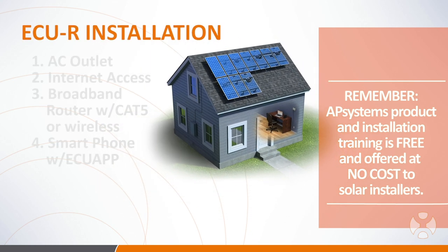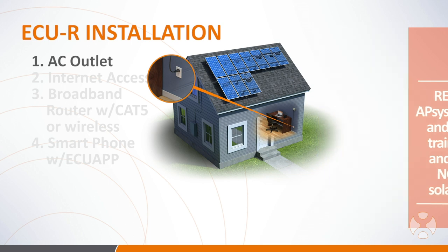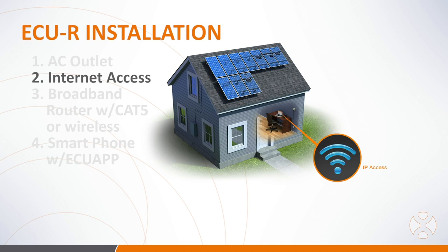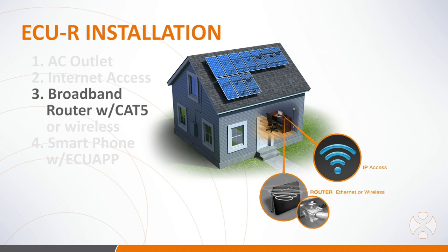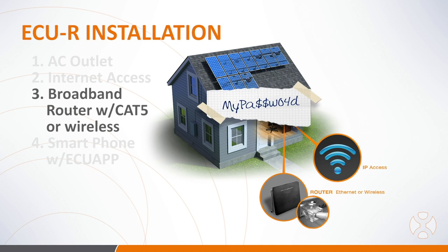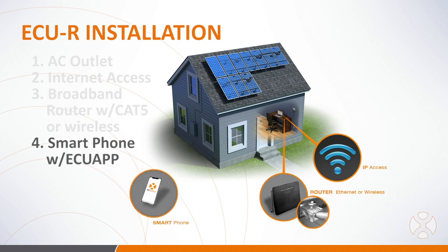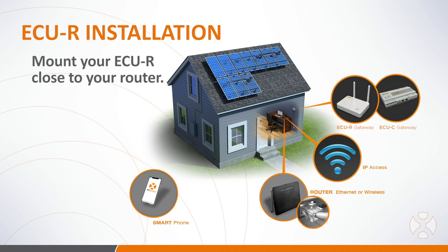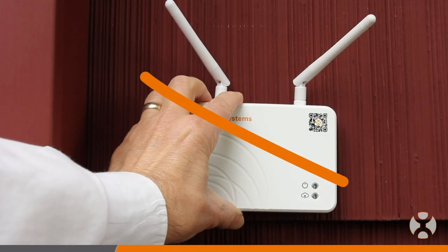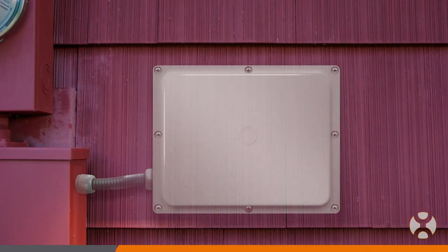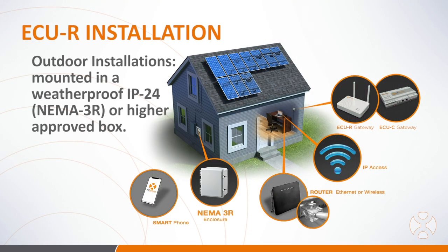In preparing to install the ECUR, be sure to have the following necessary components available: a dedicated standard AC electrical outlet located as close to the array as possible, a broadband internet connection, a broadband router with a CAT5 ethernet connection or a wireless router — if wireless, obtain the router password from the home or site owner — and a smartphone with the AP Systems ECU app installed. Note that a smartphone with Wi-Fi capability is required. When selecting an installation location, choose a spot close to the homeowner's router. Be aware the ECUR is not rated for outdoor use; if outdoor installation is required, enclose it in a weatherproof IP24 or NEMA 3R or higher electrical box.